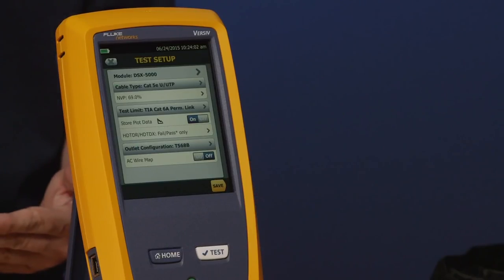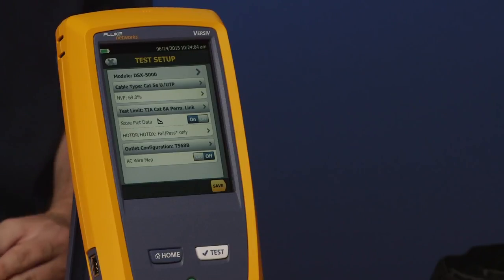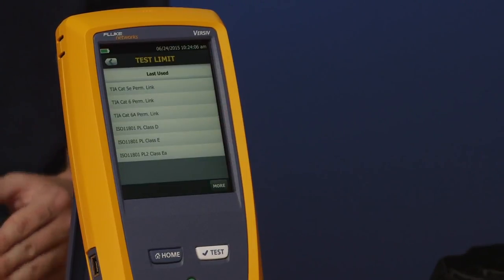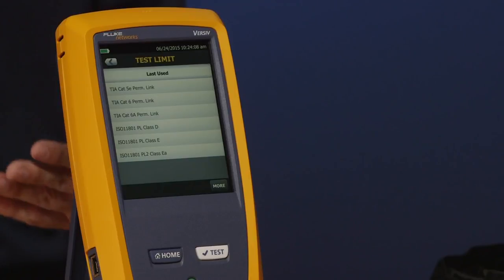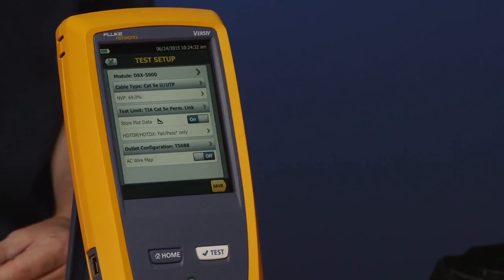Probably the most important thing is our test limit. Go ahead and tap test limit. Just like cable type, the last-used options appear. This is a brand new instrument, so we've put up the six most common test limits you typically come across — mainly permanent link, because most testing is done for warranty applications. We have the three TIA standards and the three most common ISO standards. We're going to be selecting TIA Cat5e permanent link, so go ahead and select that.